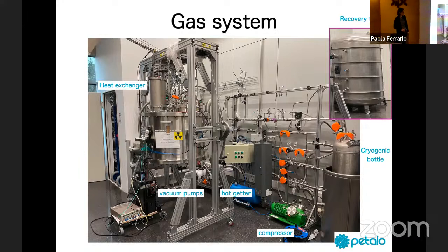And finally, this is a cryogenic bottle, which is what we use. This is just for emergency, so we haven't used it so far. But for normal operations, when we want to open the detector to make some changes or whatever, what we do is recover the gas inside this bottle with liquid nitrogen, by difference of pressure. We close the bottle, and then we can open the detector.